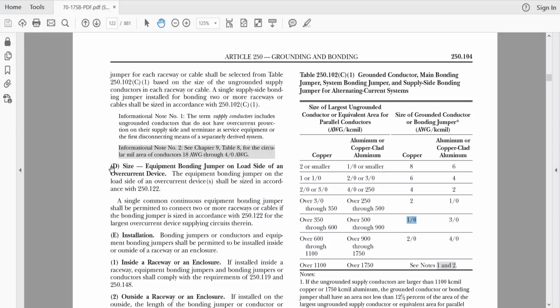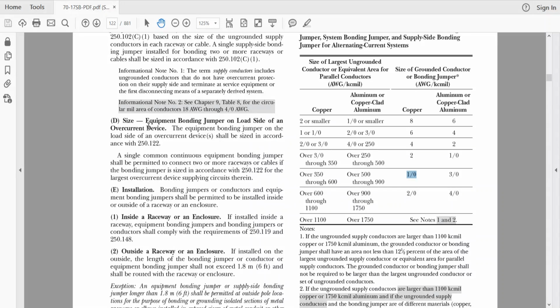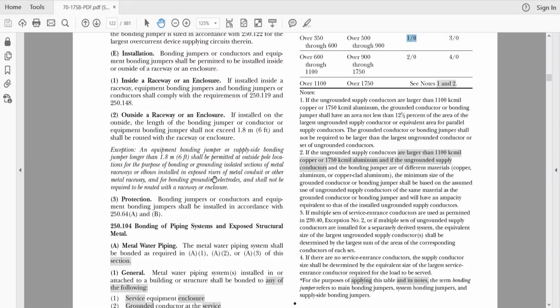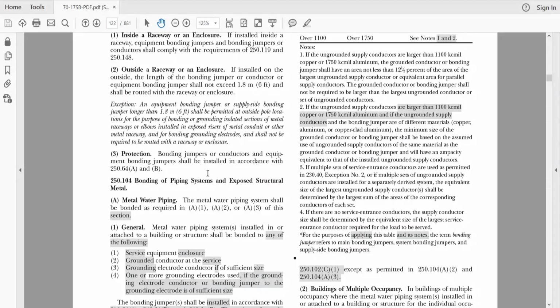Now, this was the D, which we didn't show, but if you are installing equipment bonding jumpers on the load side, you would size those bonding jumpers based on 250.122. We're not talking about those. We're talking about the use of the service conductors. In 250.122, for equipment bonding jumpers on the load side, that's all based on the overcurrent protective device, okay? Because that's what 250.122 is based on.